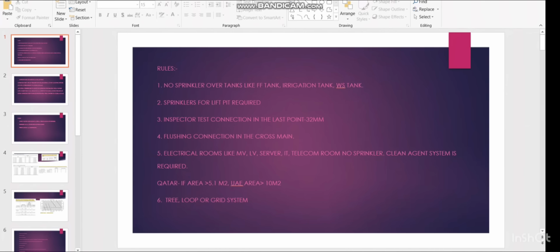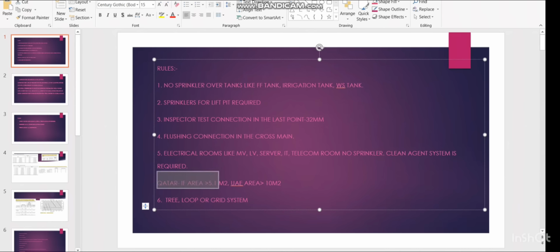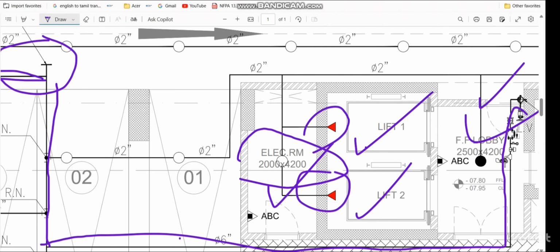As per Qatar civil defense, if the area exceeds 5.1 meter square, we have to provide the clean agent system. Similarly, for the UAE, if the area exceeds 10 meter square, we have to provide the clean agent system. So in our case, for example, this is the Qatar drawing. In the Qatar drawing, the area is more than 5.1 meter square. So this is the first mistake. Here we have provided the pendant sprinkler. This is not correct. We have to provide the clean agent system for this electrical room.